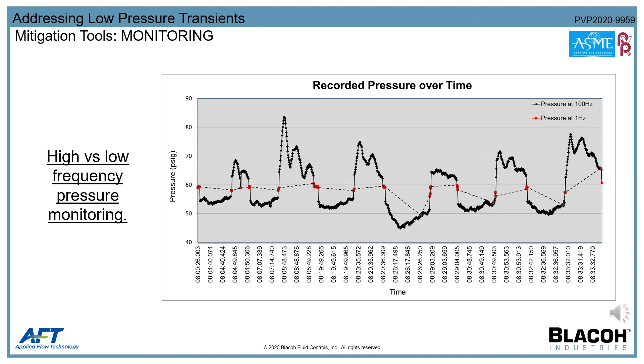The minimum recommended monitoring frequency is dependent on the system's wave speed and communication time. Generally, the higher the frequency, the more accurate and all-encompassing the data will be. Historically, the biggest challenge with higher frequency pressure detection devices has been data management, but the technology continues to advance and now includes cloud-based database capabilities.